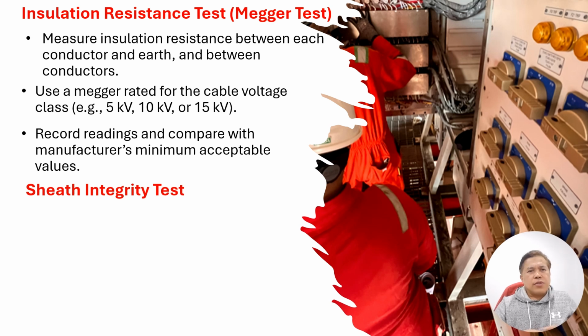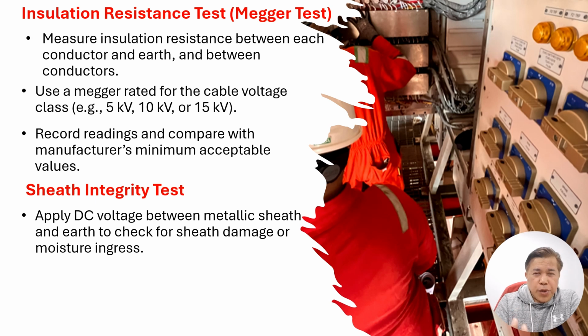Okay, so the sheath integrity test, actually we do that in the factory as well. Apply a DC voltage between the metallic sheath and earth to check for sheath damage or moisture ingress. Basically, during construction we mostly don't do this, but it is applied during factory acceptance testing.